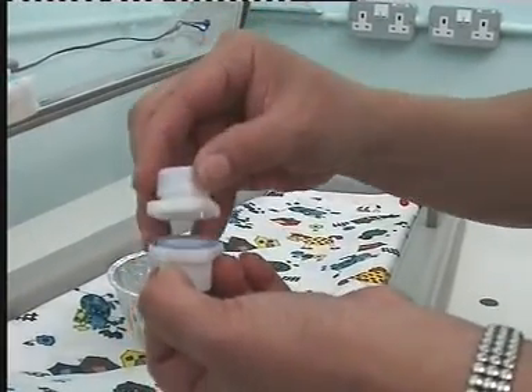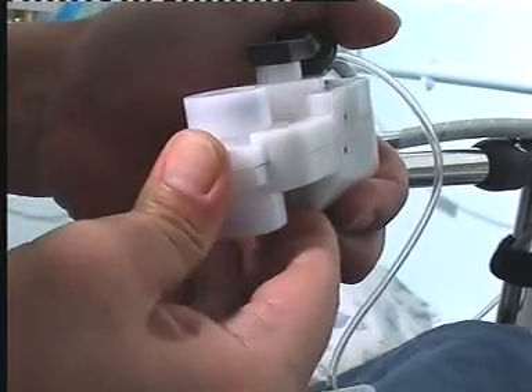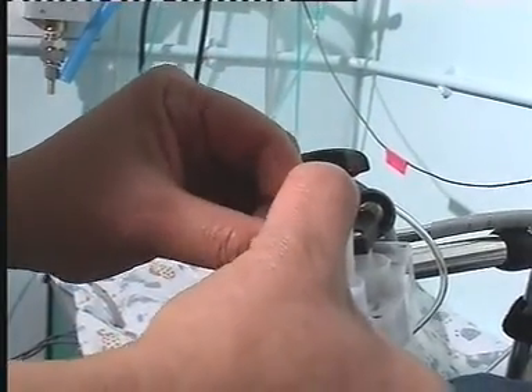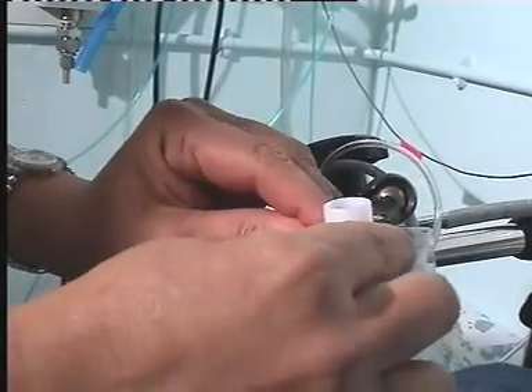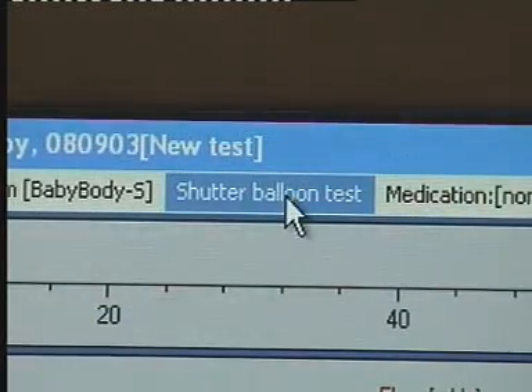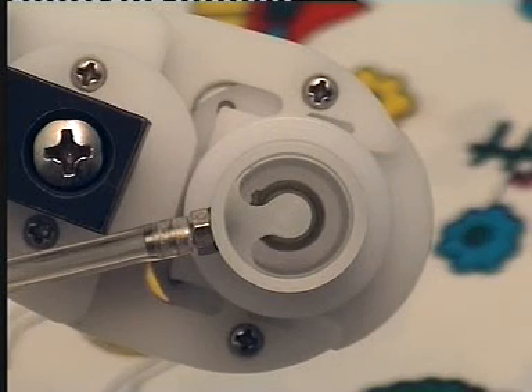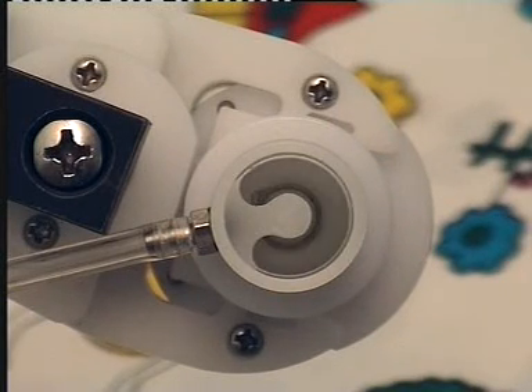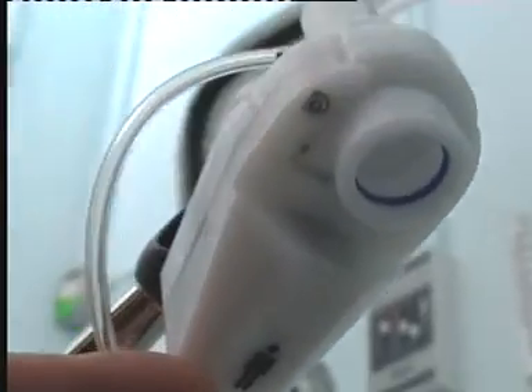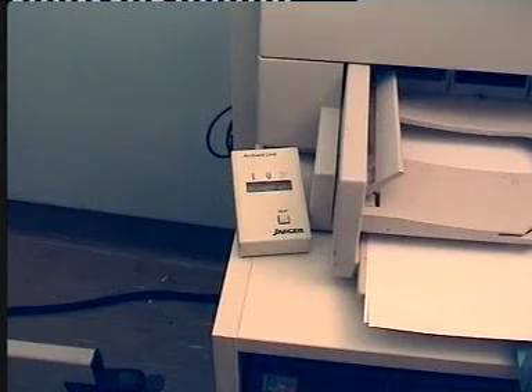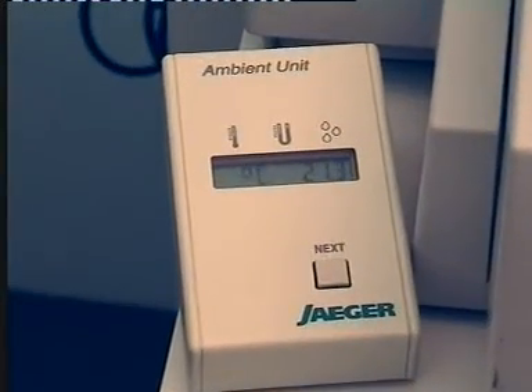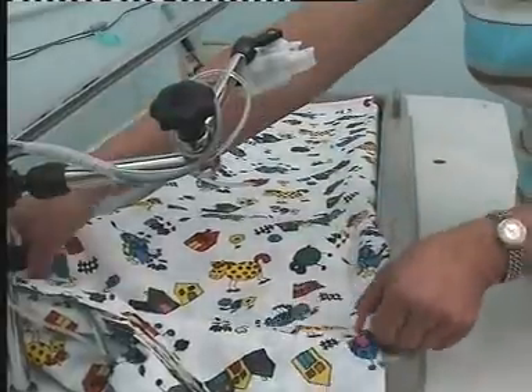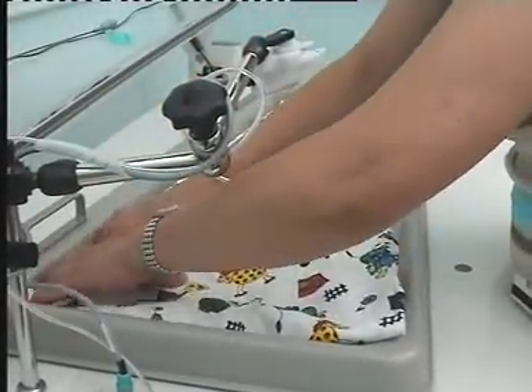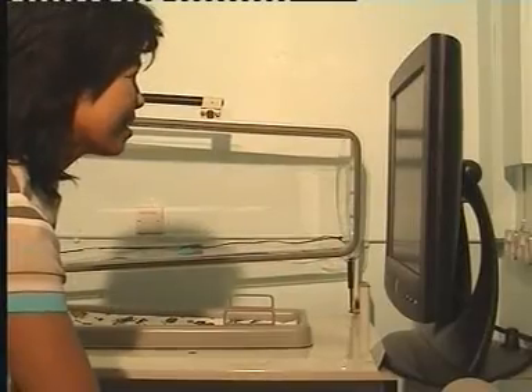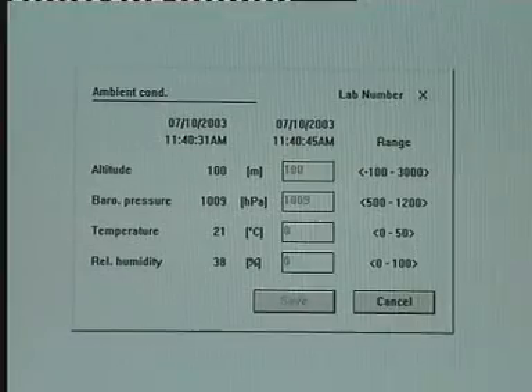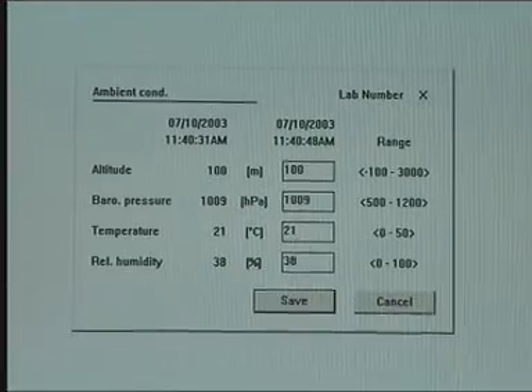Here you can see the pneumotach being assembled and placed within the transducer housing. The low dead space shutter is then clipped into place. A balloon shutter test is performed to ensure that occlusions can be held up to an airway pressure of at least 3 kilopascals. The patient icon must face towards the patient when in use. Room temperature should ideally be maintained between 21 and 25 degrees Celsius, and the test performed in a room where the lighting can be dimmed and noise levels minimized. Details of ambient conditions are entered each day so that recorded signals can be corrected to BTPS conditions.